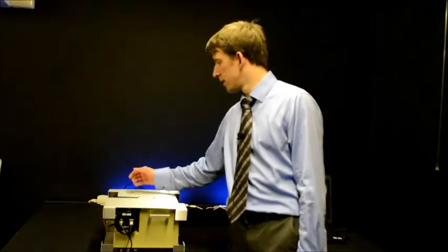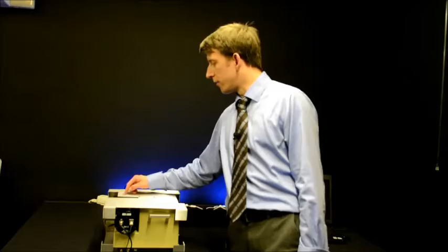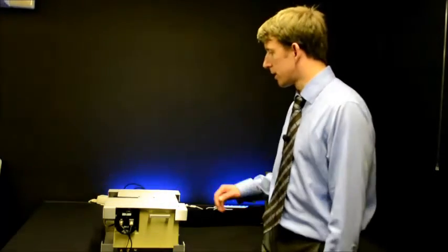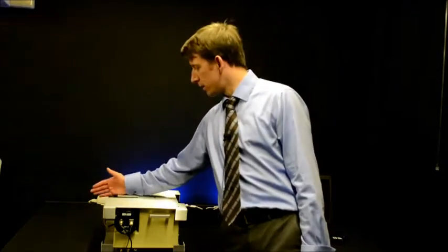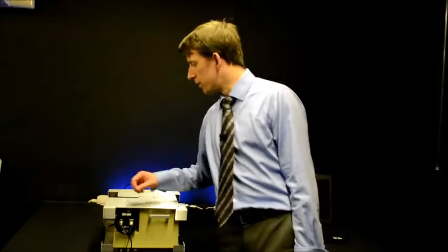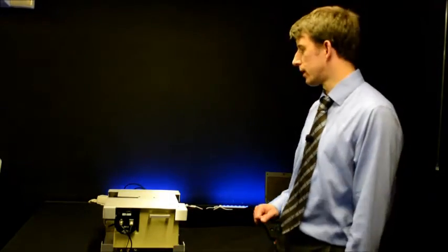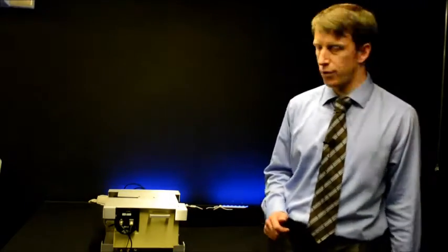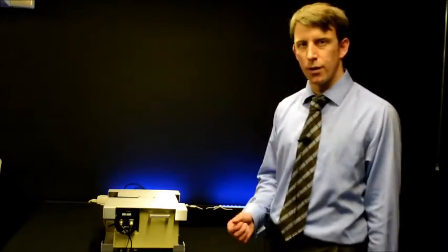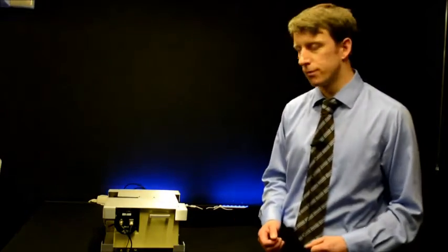We have a spherical mirror, diffraction grating, spherical mirror, and a plane mirror coupling light either to the exit port with a photomultiplier or the exit port in which the RSR unit is placed for the characterization of radiometers. And this mirror is mounted on a solenoid, a swing-away mirror, which can be controlled through a computer.